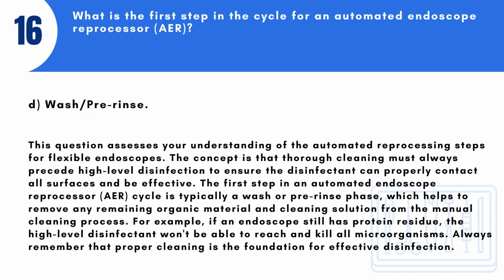The first step in an automated endoscope reprocessor (AER) cycle is typically a wash or pre-rinse phase, which helps to remove any remaining organic material and cleaning solution from the manual cleaning process. For example, if an endoscope still has protein residue, the high-level disinfectant won't be able to reach and kill all microorganisms. Always remember that proper cleaning is the foundation for effective disinfection.